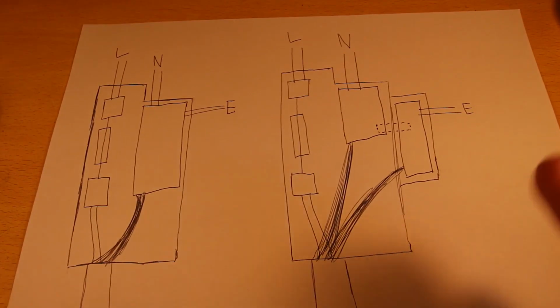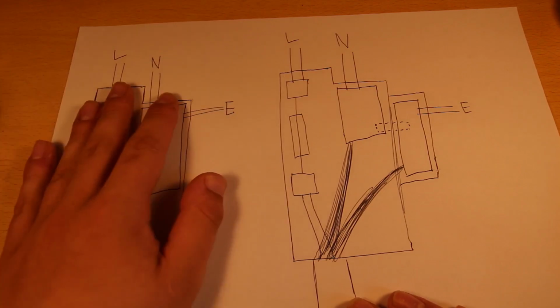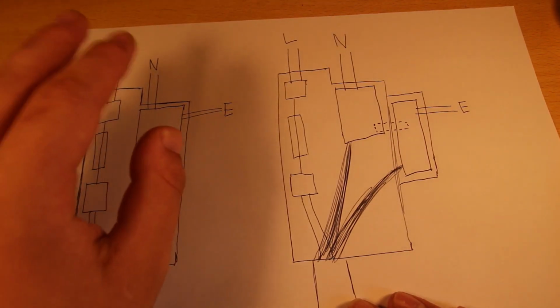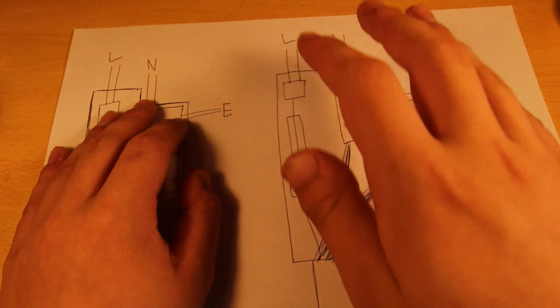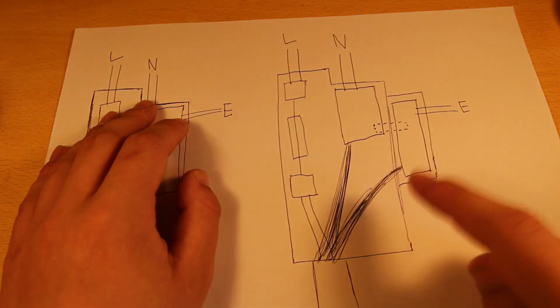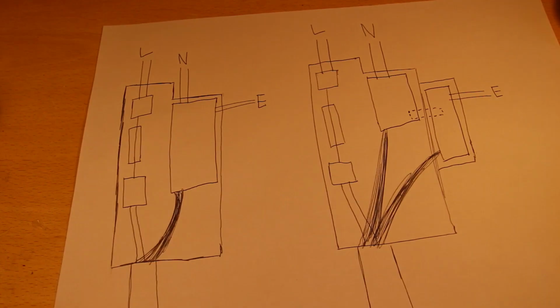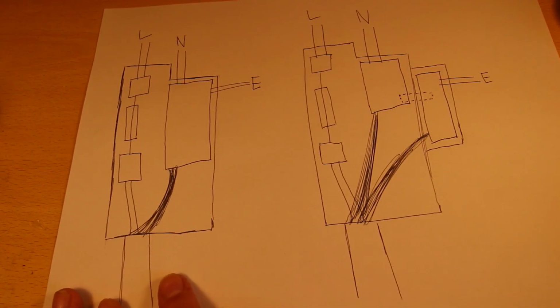In your house, the cable which comes from the substation into your house is terminated into a thing known as a service head. Ideally I would have one to show you, but I couldn't get one on short notice, so next best thing is a diagram, which I have here. There are 2 main types of service head you will find. This one is used for TT and TNCS, and this one is used for anything really, but mostly for TNS applications. The incoming cable at the bottom here is the one that comes from the substation.